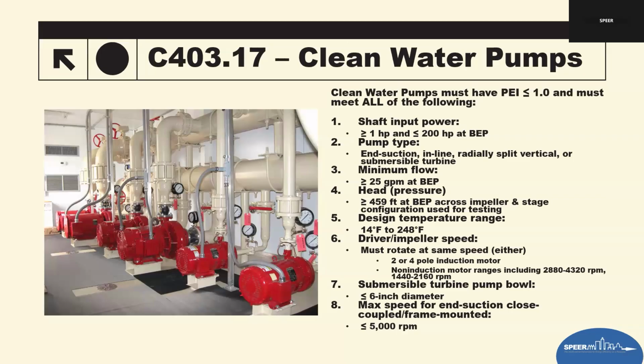For the pump types covered, the code narrowly defines the pump types in these sections. Applicable pumps include end-suction close-coupled, end-suction frame-mounted, inline pumps, radially split vertical pumps, and submersible turbine pumps. This aligns with DOE's test procedures for clean water pump efficiency.